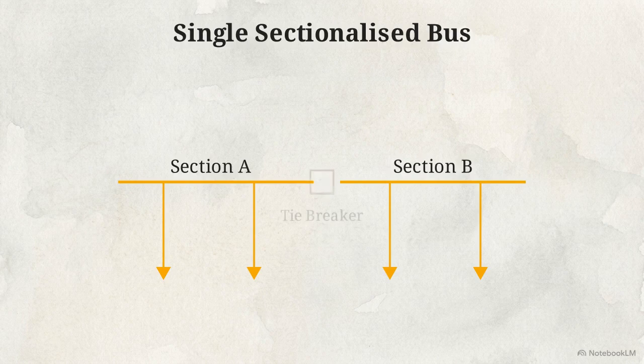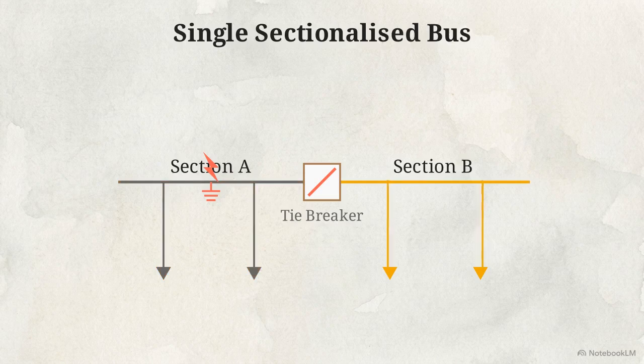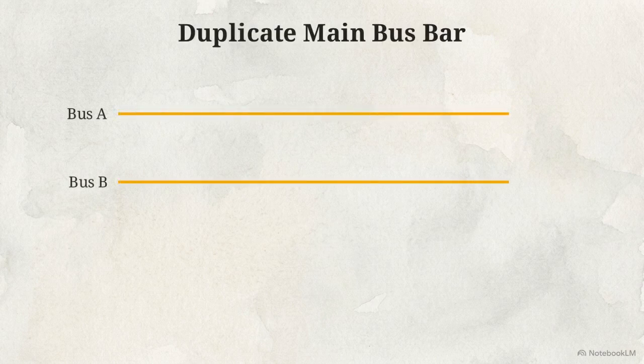To prevent total shutdown, we use the single sectionalized bus scheme. The bus divides into section A and B, connected by a tiebreaker. If a fault strikes bus A, the breaker opens. Bus A goes dark, but power through bus B continues unaffected. To push reliability further, engineers developed the duplicate or double main busbar.